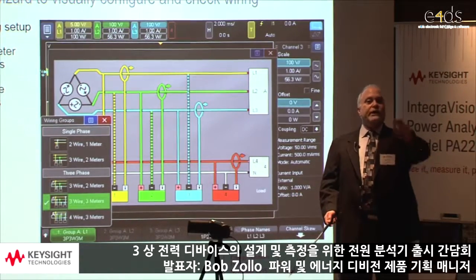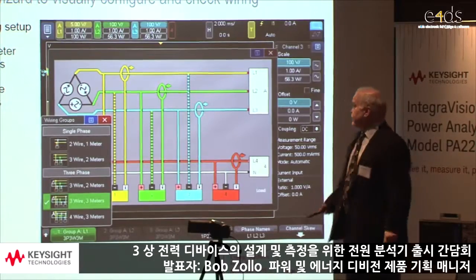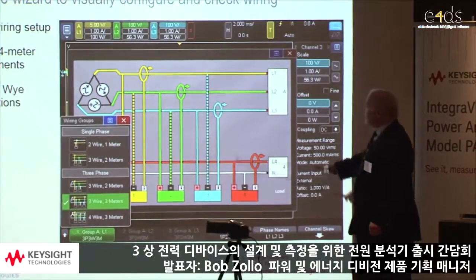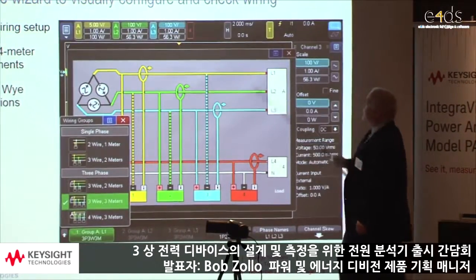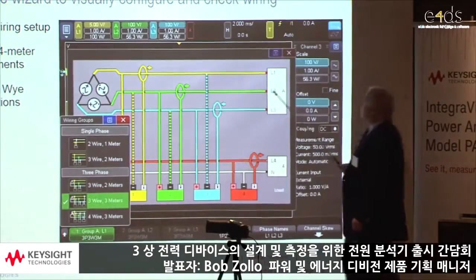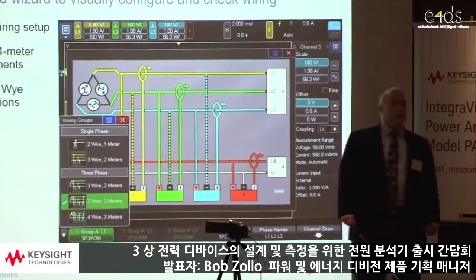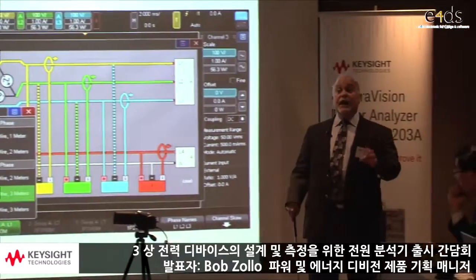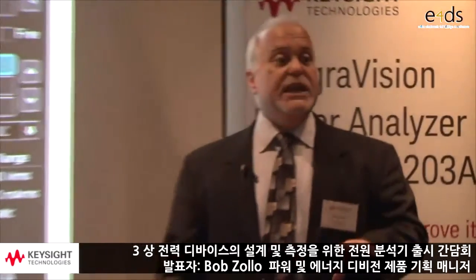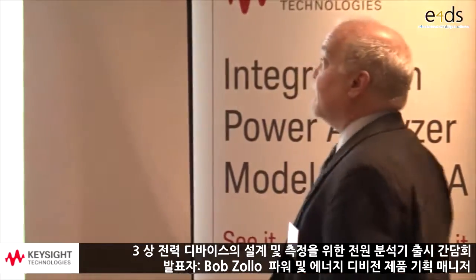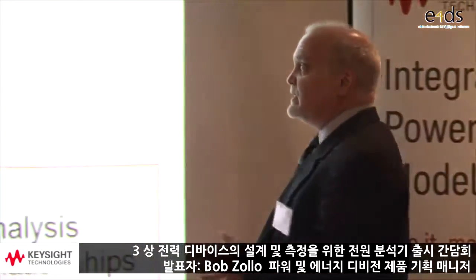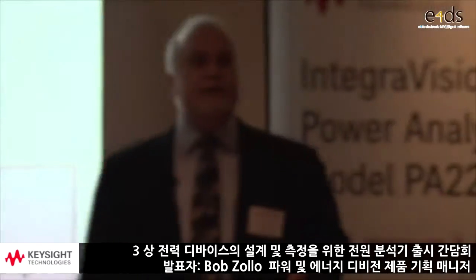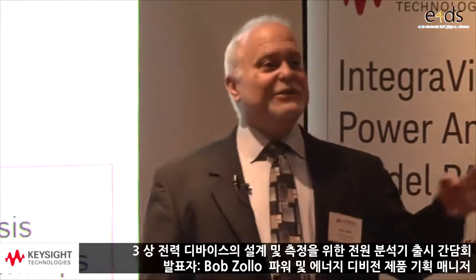Tell it what you want, it will tell you how to wire it up. It gives polarity of signals, it tells you where to make the connections from the power system to the device that you're trying to measure. So this is an easy way to help customers, to help engineers ensure that they're correctly connected. Excellent. Now, once you're correctly connected, the next thing that you want to do is verify that you're connected correctly.